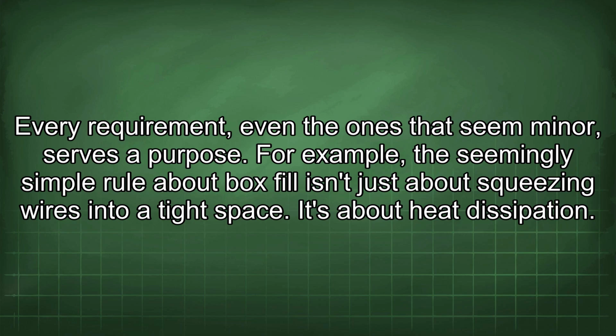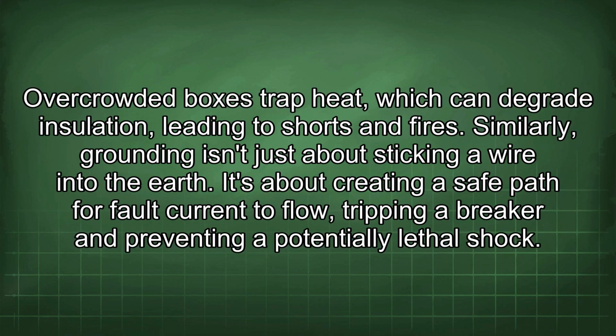For example, the seemingly simple rule about box fill isn't just about squeezing wires into a tight space. It's about heat dissipation. Overcrowded boxes trap heat, which can degrade insulation, leading to shorts and fires. Similarly, grounding isn't just about sticking a wire into the earth. It's about creating a safe path for fault current to flow, tripping a breaker and preventing a potentially lethal shock.